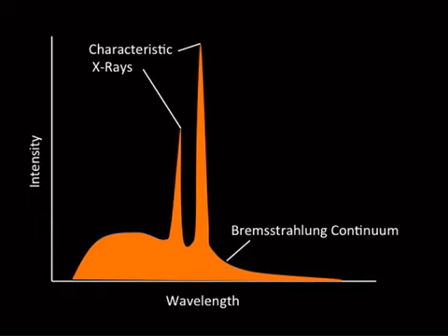Now, a couple of other things. I mentioned that tungsten is used for specific reasons. One of them is that the K-shell binding energy is proportional to Z squared. So a lower Z material gives lower energy X-rays, and a higher Z material will give higher energy X-rays. So that's another reason why whoever decided to use tungsten decided to use it.